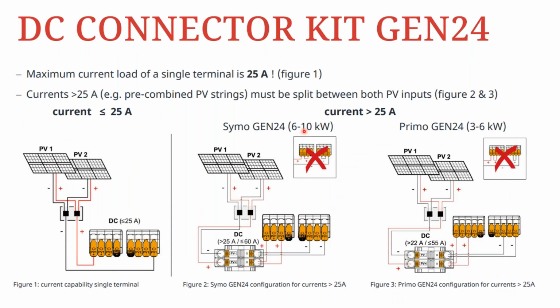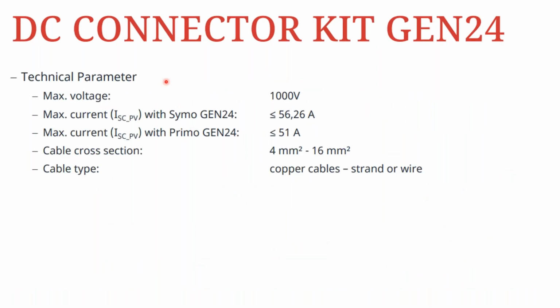When it comes to the connection itself, when you design a string which generates more than 25 amps, maybe you want to pre-combine these strings, but still want to do a connection to a GEN24 Plus inverter, then we recommend to do a connection using the DC connector kit, so that instead of going directly to the inverter from the modules, you connect, as you can see here, for the Symo GEN24 with a DC connector kit that would allow something that is equal or slightly less than 60 amps to be connected now between the two MPPTs. And for the Primo GEN24, the DC connector kit would allow something in the range of 22 amps to a maximum of 55 amps to be connected to the two MPPTs within the Primo GEN24. The technical parameters of the DC connector kit: it can operate at a maximum voltage of 1000 volts.